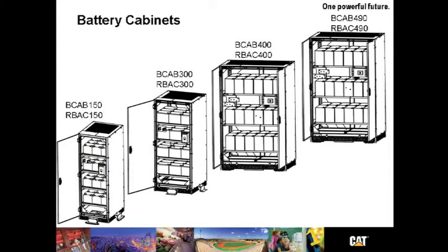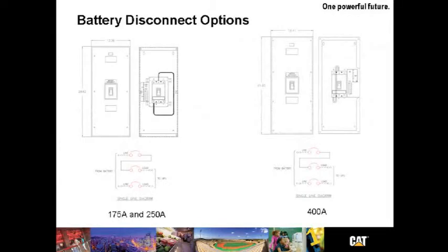Let's talk about battery cabinet options. Caterpillar offers adjacent and remote battery cabinets. The adjacent cabinet provides a matching battery cabinet loaded with VRLA batteries for installation adjacent to the UPS cabinet. Connection cables to the UPS are provided by Caterpillar, but not with the remote cabinets. Each battery cabinet is provided with a battery disconnect breaker sized for the batteries provided. Battery disconnect options are for customers who choose to provide their own batteries. A battery disconnect becomes a mandatory option because the UPS must have a way to disconnect itself from its battery source under certain conditions.